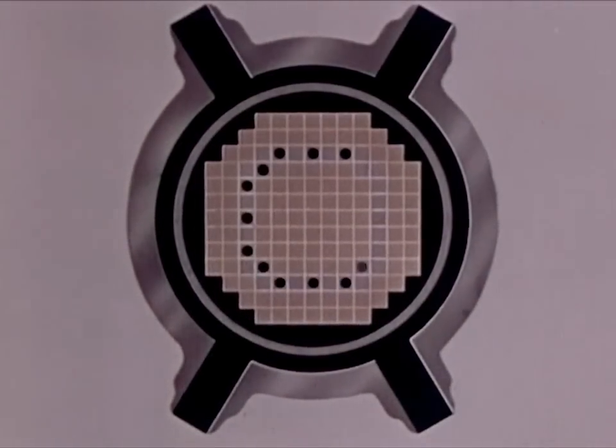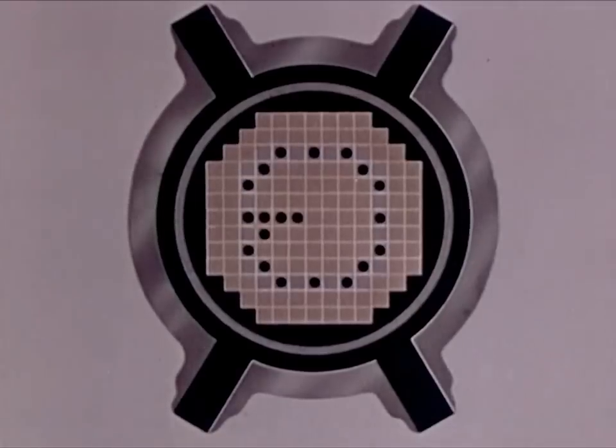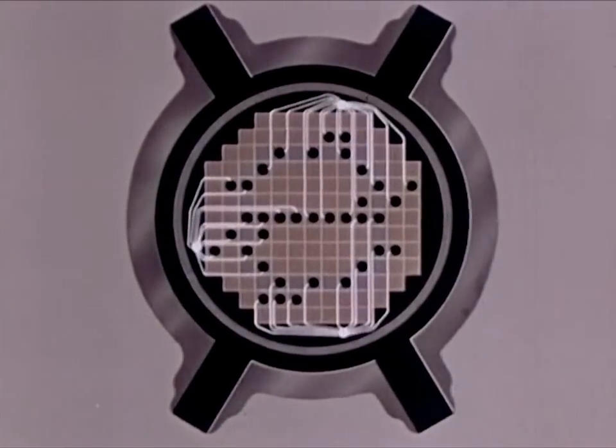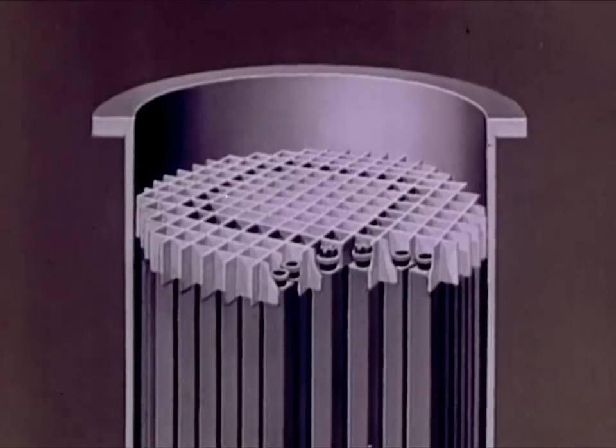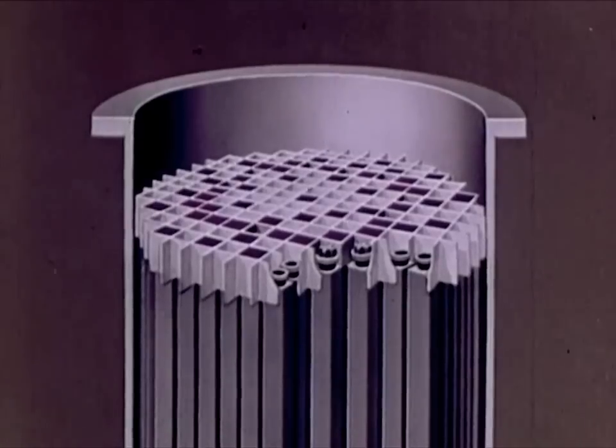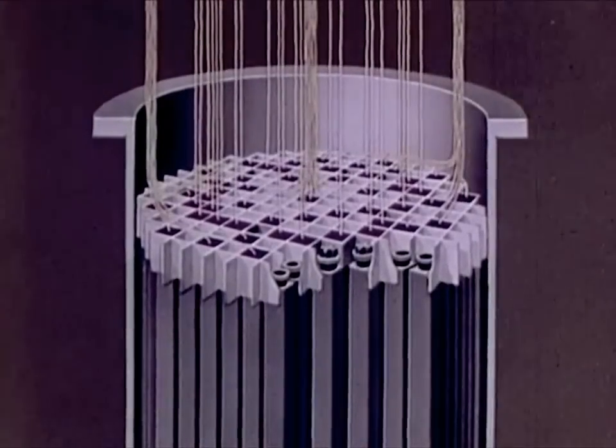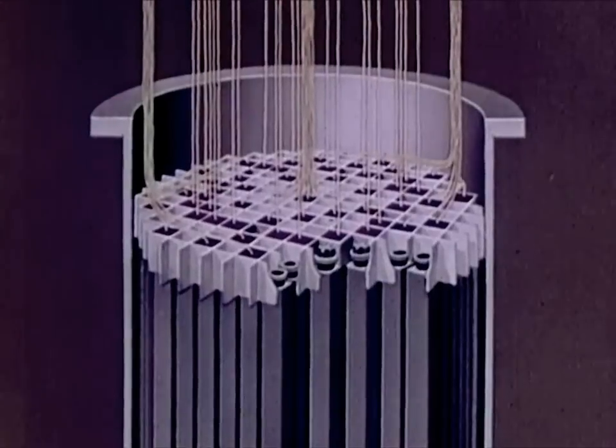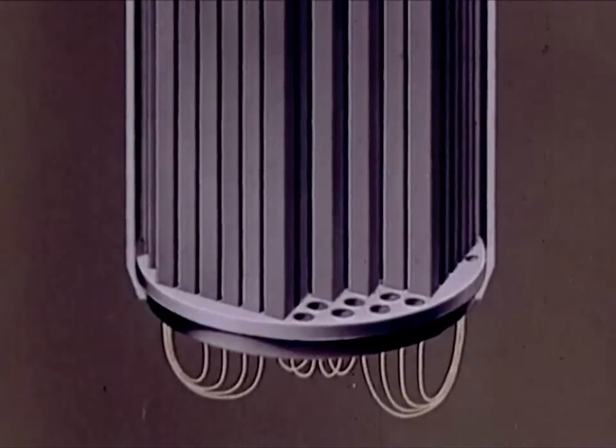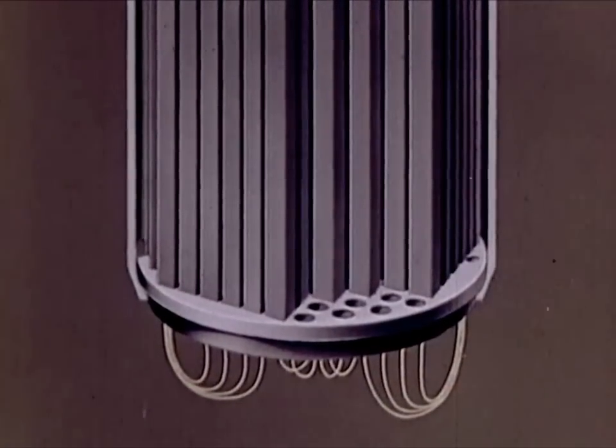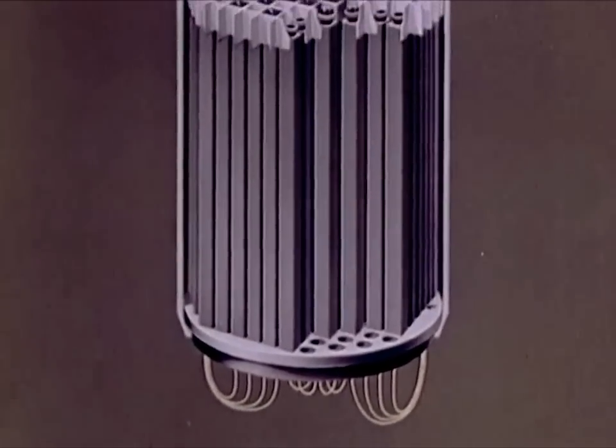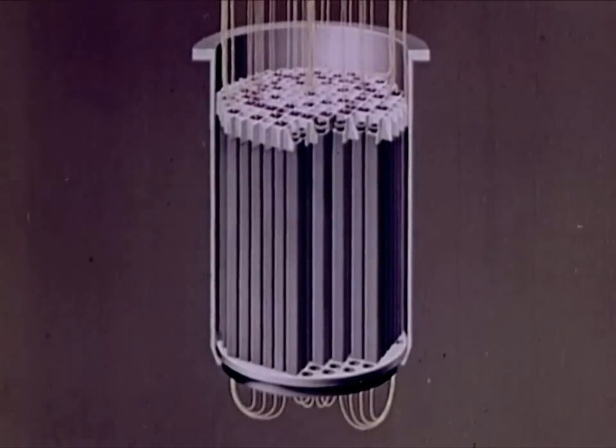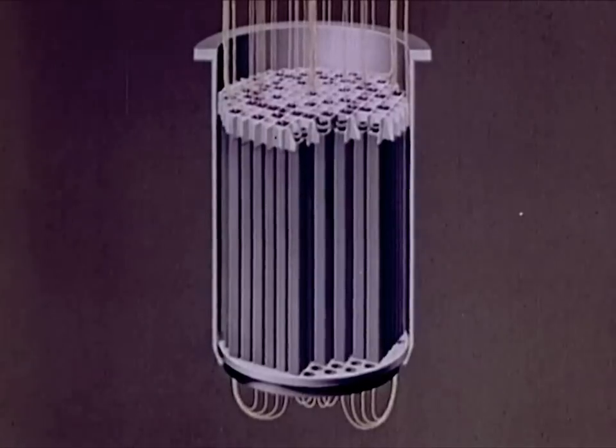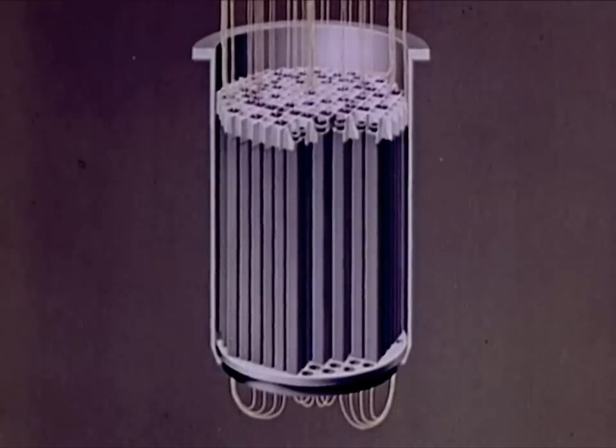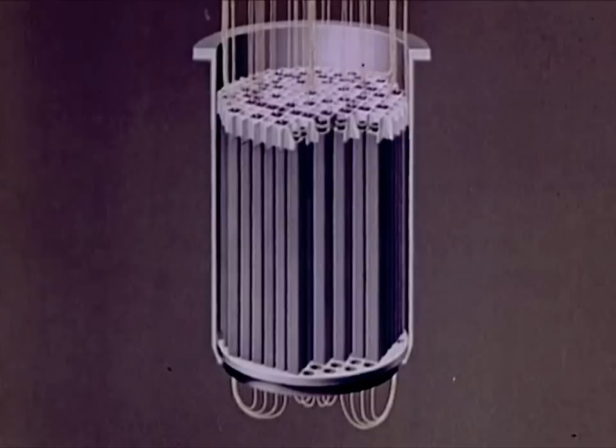Half of the seed and about one-sixth of the blanket fuel assemblies are instrumented for flow measurement. Approximately two-thirds of the seed and one-quarter of the blanket assemblies have thermocouples placed to measure the temperature of the water leaving the fuel assembly. Additional thermocouples at the bottom of the core give core inlet water temperatures. The temperature data and the flow data are used to compute power distribution in various regions of the core. Measurements which have been made indicate a good agreement with the physics calculations.